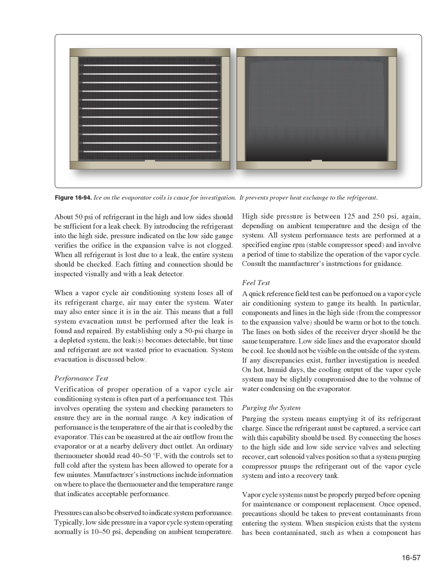Pressures can also be observed to indicate system performance. Typically, low side pressure in a vapor cycle system operating normally is 10 to 50 pounds per square inch, depending on ambient temperature. High side pressure is between 125 and 250 pounds per square inch, again depending on ambient temperature and the design of the system. All system performance tests are performed at a specified engine RPM and stable compressor speed, and involve a period of time to stabilize the operation of the vapor cycle. Consult the manufacturer's instructions for guidance.